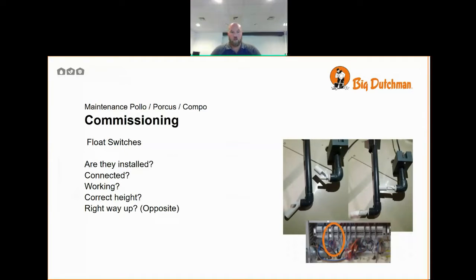The float switches, are they installed? Are they connected? Are they working? Are they at the correct heights? And are they the right way up? The Euro system, they are in opposite directions. The minimum float falls open, the maximum float lifts open. So in the standard water level, both switches will be closed as per the right picture. Check that the floats are correctly installed.